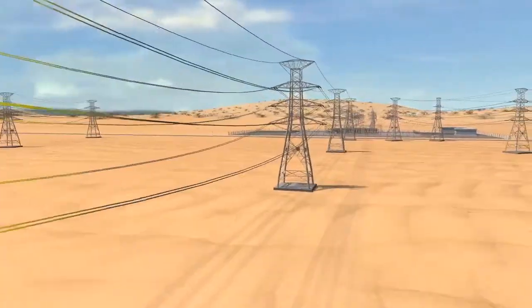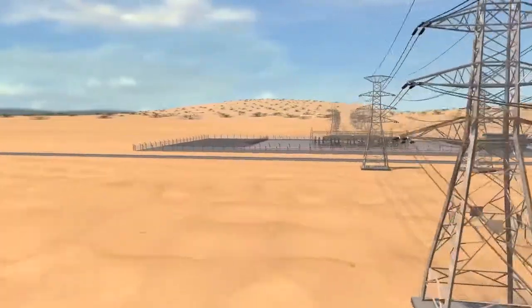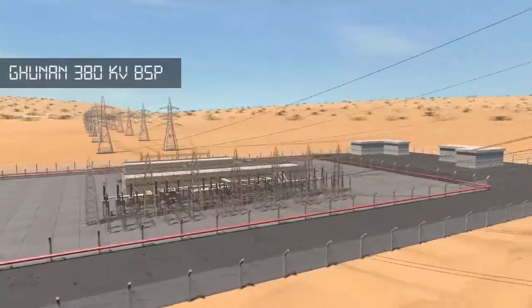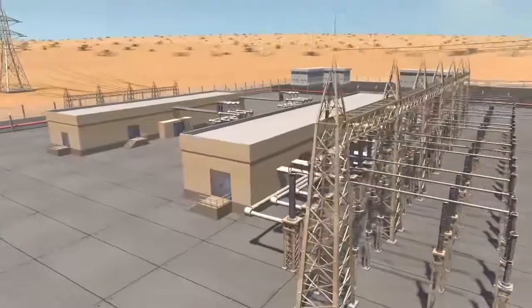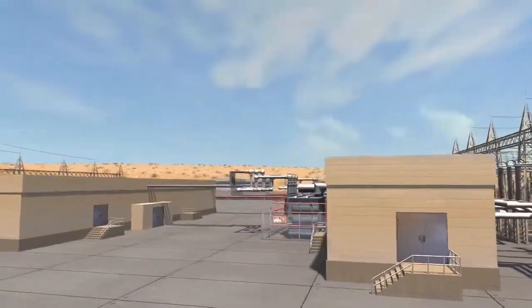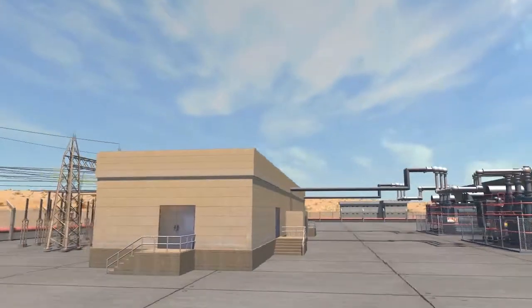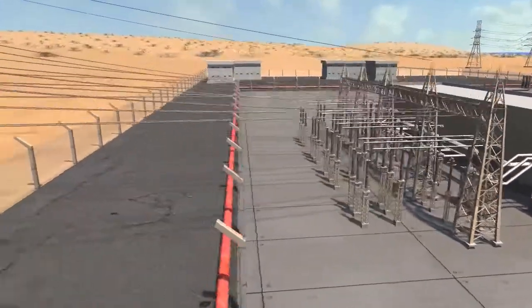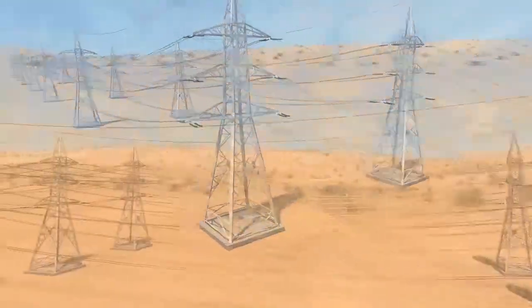The 380 kV is provided if the electrical power is necessary to be transmitted to far cities, whereas the 230 kV is used for power transmission in near cities. Switching stations are such as bulk supply points, BSP, and grid stations. 380 kV or 230 kV transmission voltage levels mostly exist in bulk supply points, which are located at the boundary of the city.